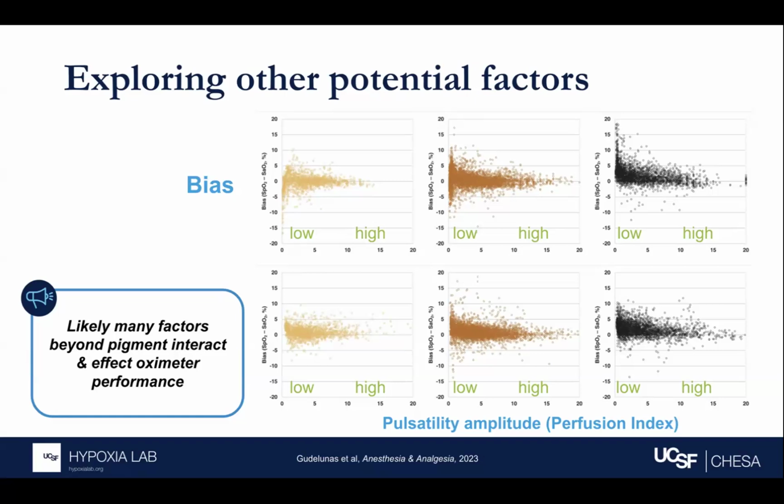So one of the reasons this is relevant is when manufacturers are testing their devices for regulatory purposes, it is standard practice to induce high perfusion, to actually warm people's hands, to all sorts of methods deployed to actually make the perfect signal. And so how predictive, how relevant is laboratory testing of these devices for regulatory purposes when in the real world, that's not what they're subject to. And so we have been trying to tease that out a bit more.